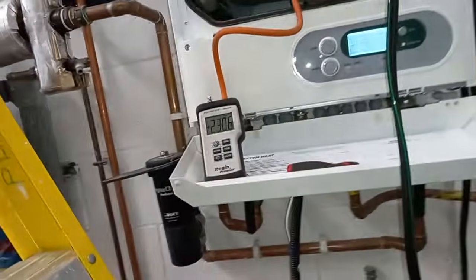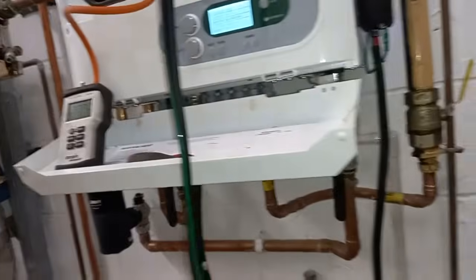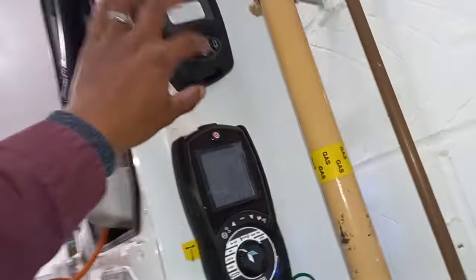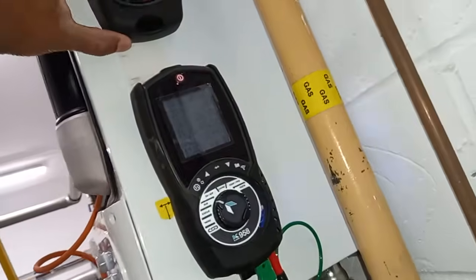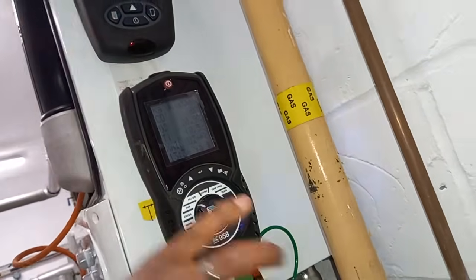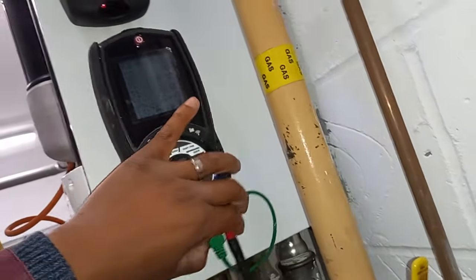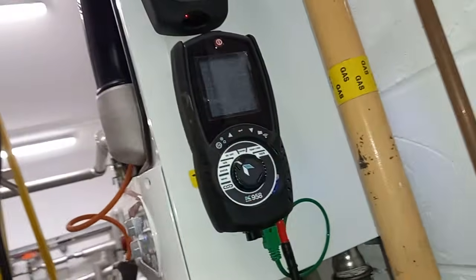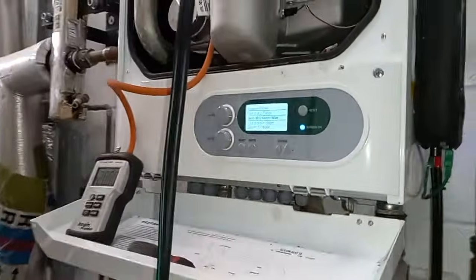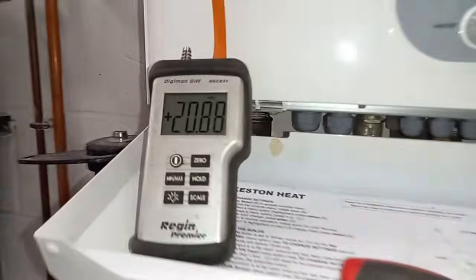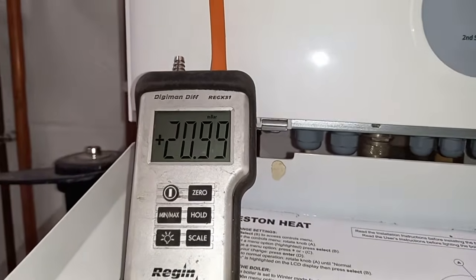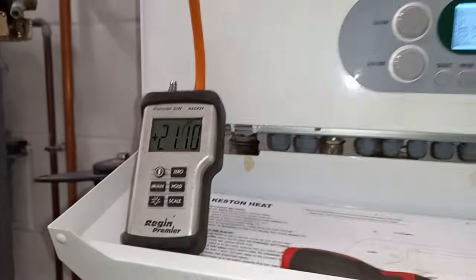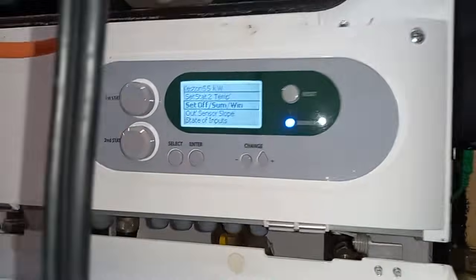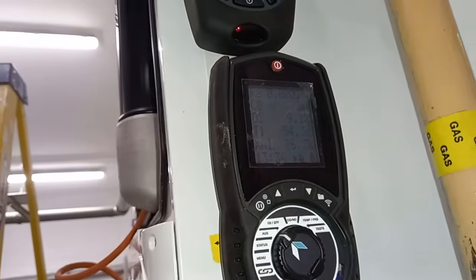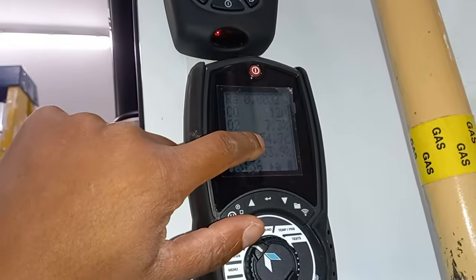And I'm going to check my working pressure now on high fire. I'm going to turn my printer on. Okay. And I want it to stay on for quite a while. Here's my working pressure. Yep, so I'm going to get a picture of that or write it down, that in high fire, that's my working pressure. Burner's on, give it a chance for my flue to get up to temperature.